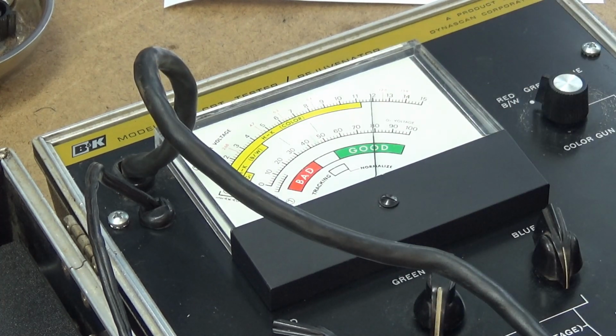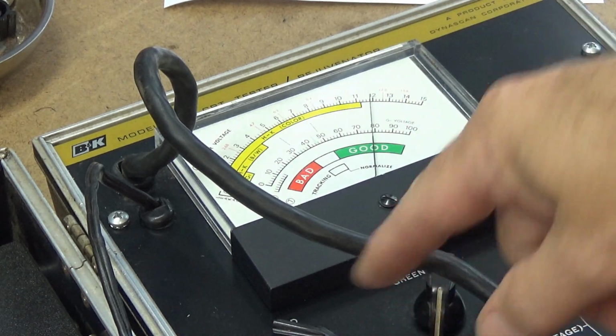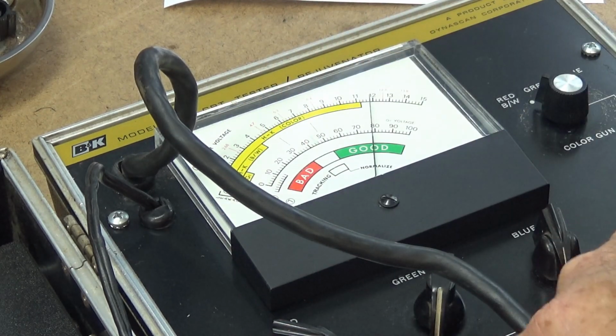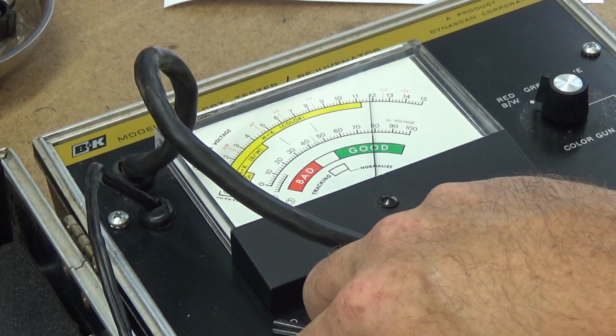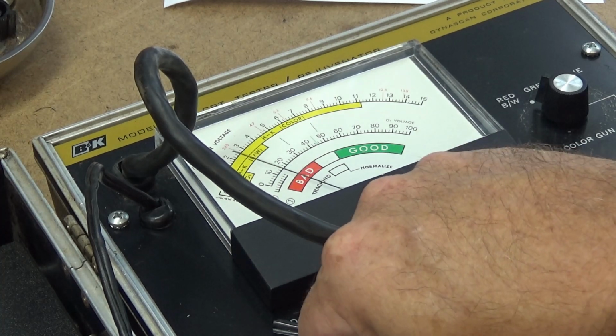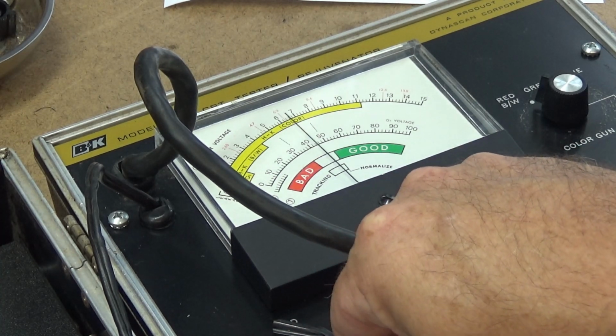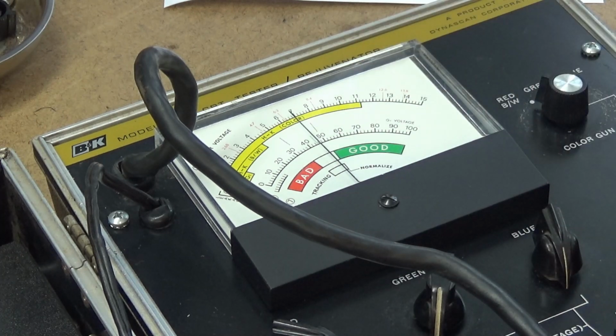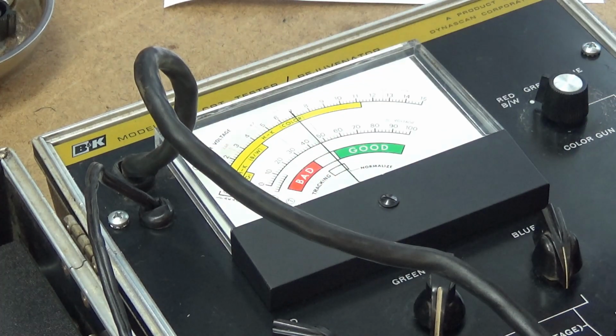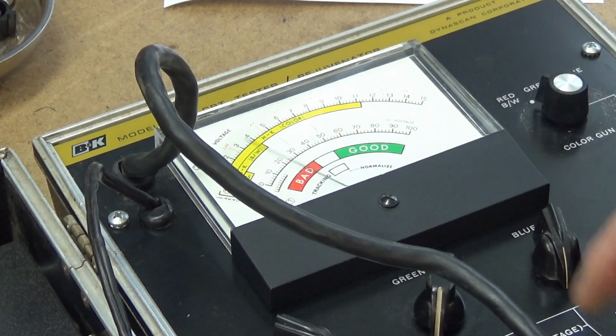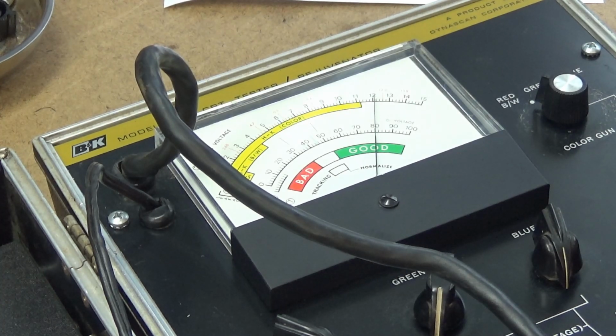Emission's good. Look at there, y'all. That's good news. I just didn't have the G1 voltage set right. I had it set way down here. It's supposed to be up here on 45. So this is a pretty easy device to use. You just follow the numbers and look at the scale, and that's how you do it. G2 voltage, I did get it to raise up just a little bit. But the emission says it's okay, and like I said, if I reduce the heater voltage, you see the emission go down.